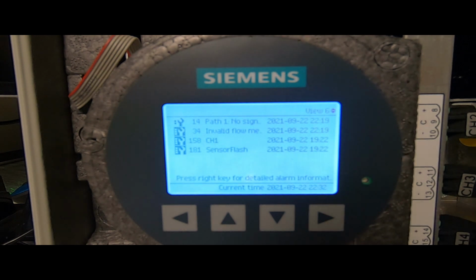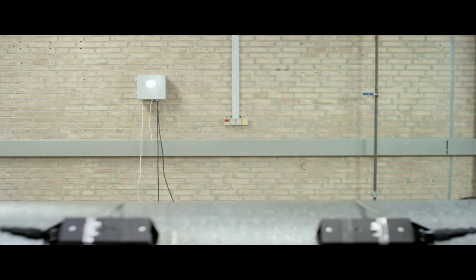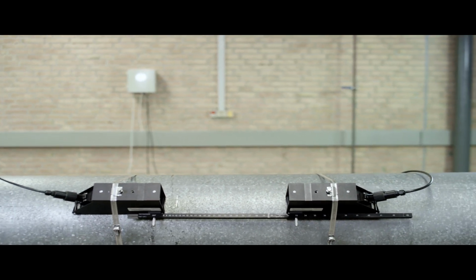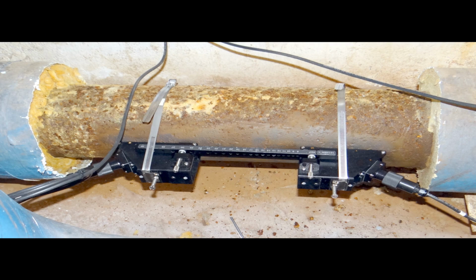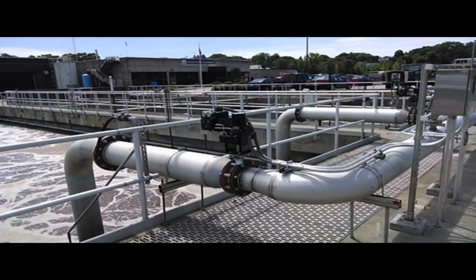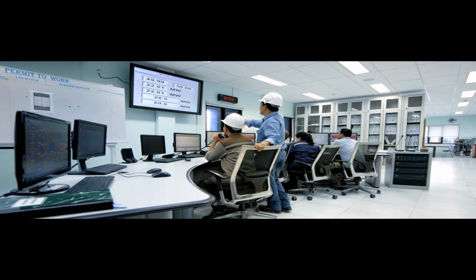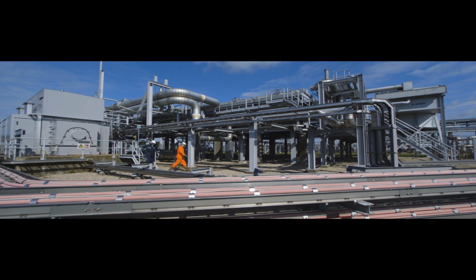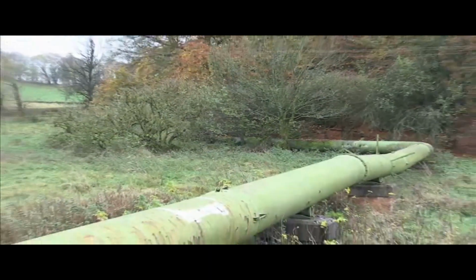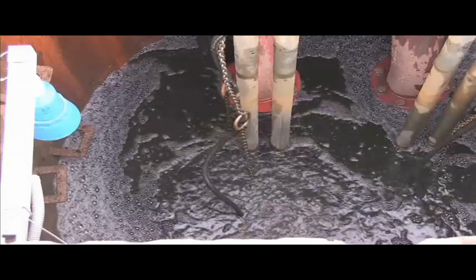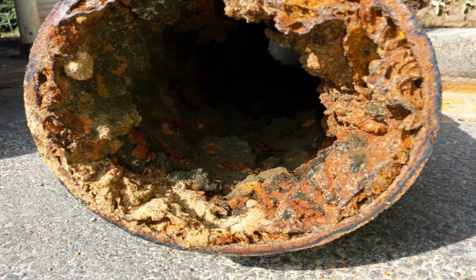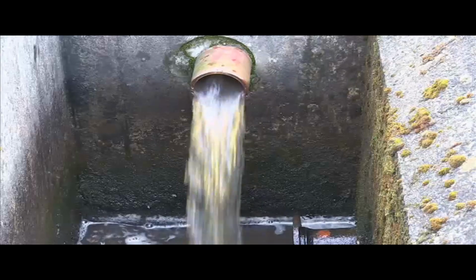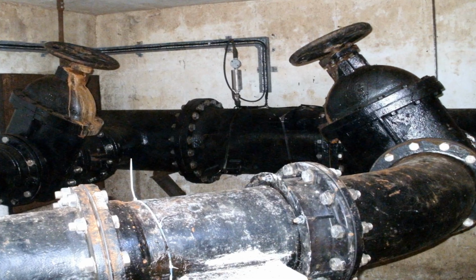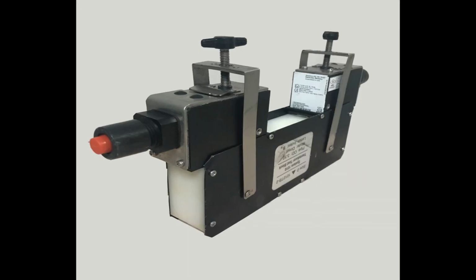In such cases, it's all too common to suspect the flow meter, yet more times than not, it isn't the meter. It's the application pipe or fluid that's to blame. So how can you troubleshoot the possible cause? In such situations where there are multiple potential sources for a problem, the best method is to separate the flow meter from the application by testing it independently.